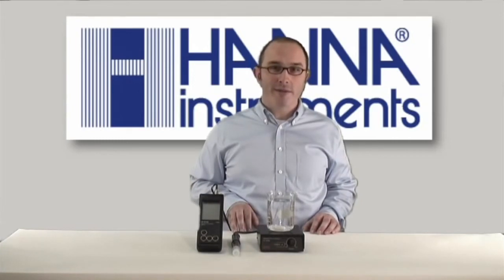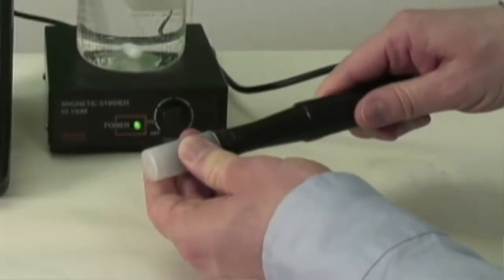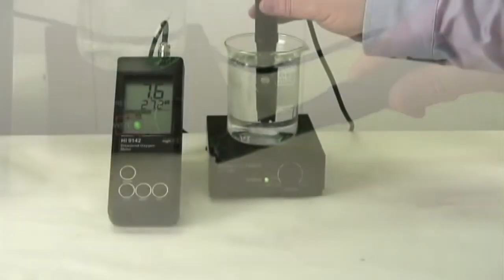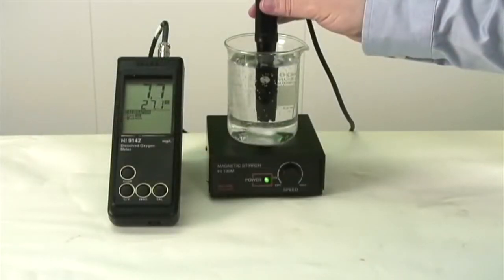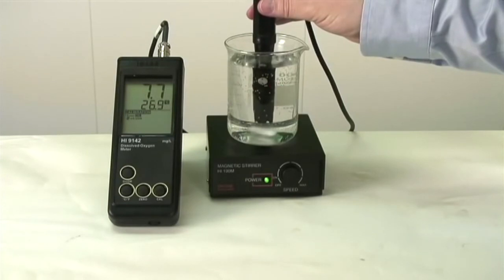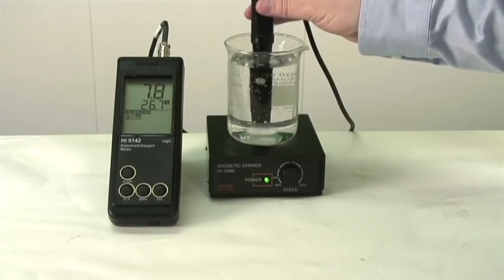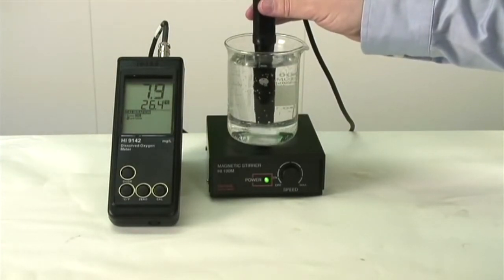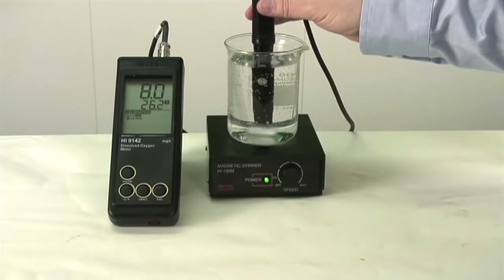Before we go, I'll show you how easy it is to take a measurement. Just make sure that your meter is calibrated and that your probe is properly polarized. Remove the protective cap and immerse the probe in your sample. Remember to submerge the temperature sensor too. Again, you want this sample to be moving, so stirring or using a stir plate is necessary. The DO and temperature values are displayed on the LCD. Once you get a value, you'll need to refer to the altitude and salinity tables in the back of your instruction manual to make any necessary corrections.